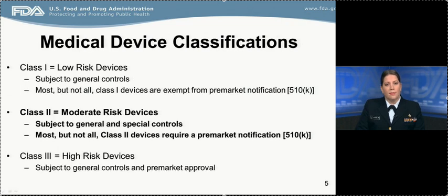The FDA regulates medical devices based on risk. Class 1 devices are considered low-risk devices. These devices are subject to general controls. Most, but not all Class 1 devices are exempt from the pre-market notification process.